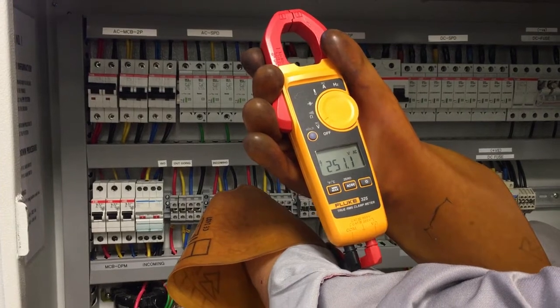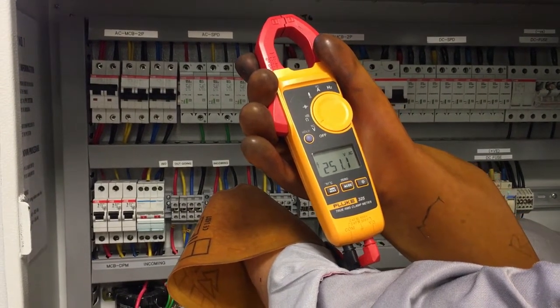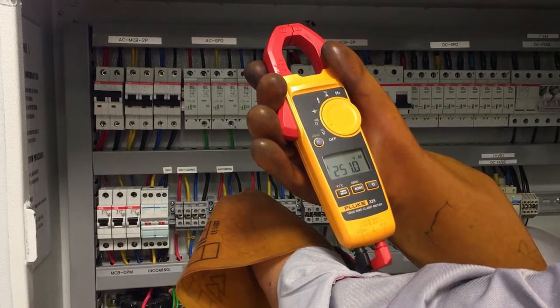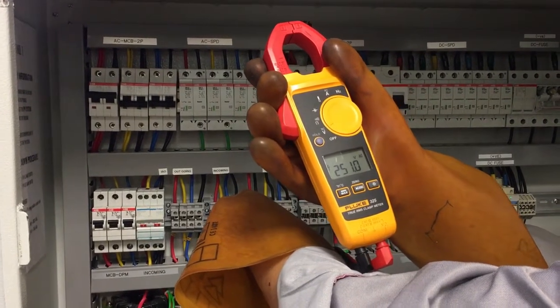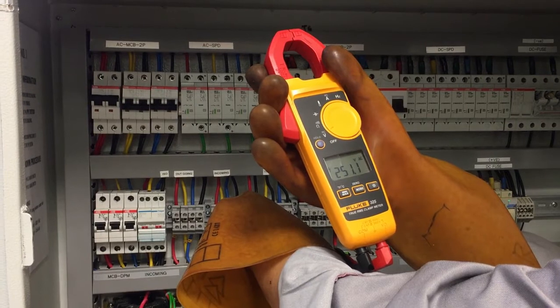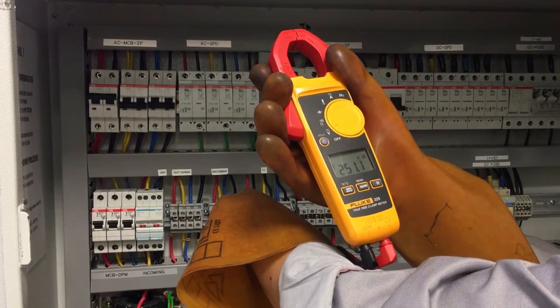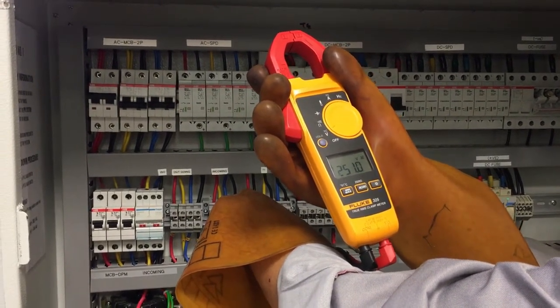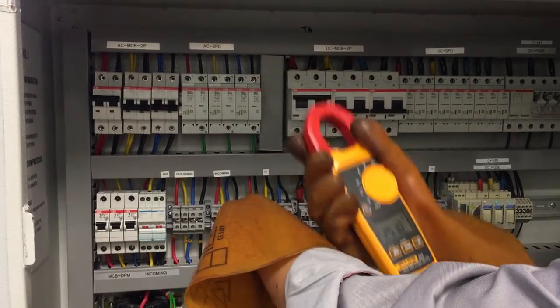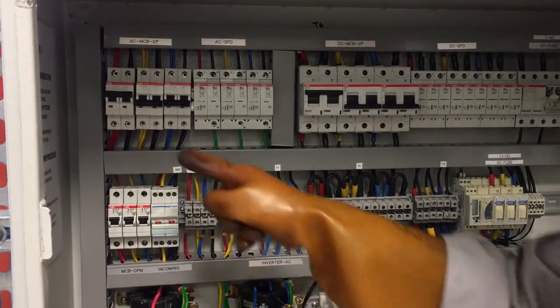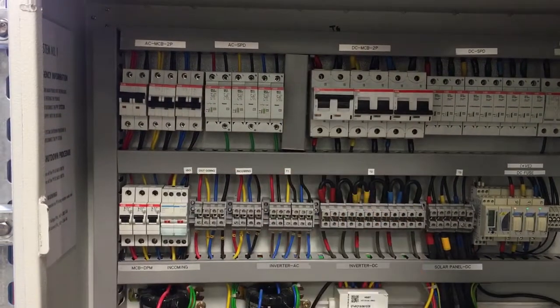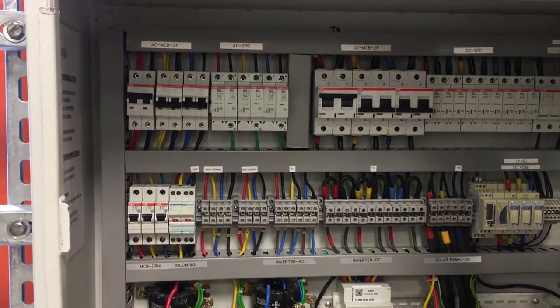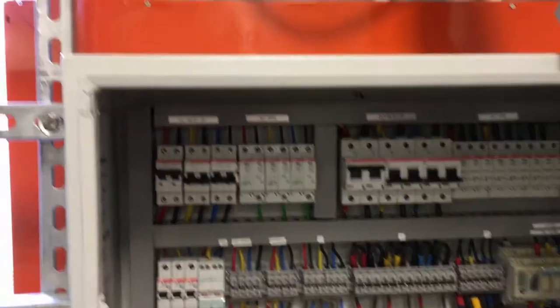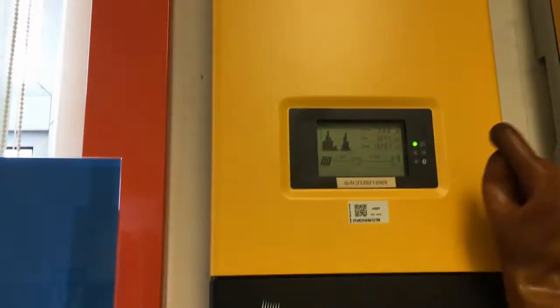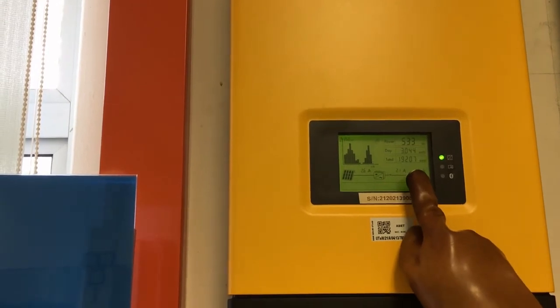Okay, so now we want to make sure that when there is a grid problem, our inverter does not supply. How do we simulate that? So anti-islanding, we simply turn off the AC MCB and verify that there is no power coming out of the inverter. Okay, so now I am going to turn off the MCB because now the circuit is energized. Alright, so if you look at the inverter now, the inverter is generating 533 watts. Now I'm going to turn off the AC MCB.